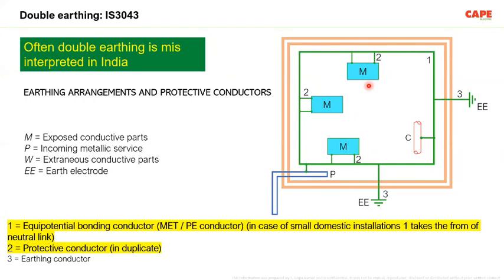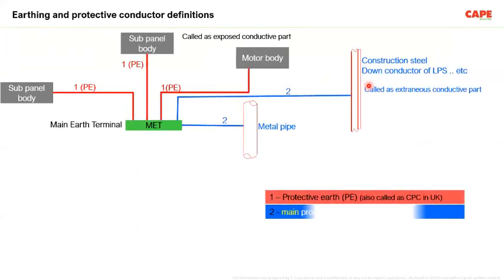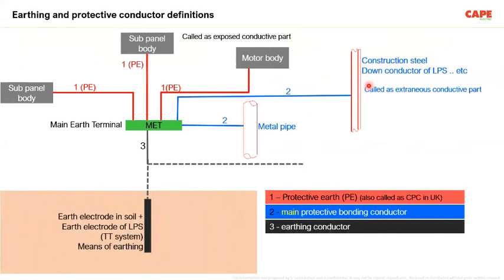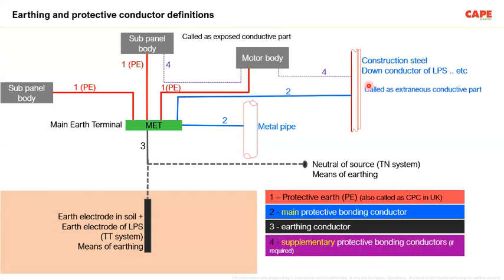What double earthing means is, you have a protective equipotential bonding in your building, and you are buying a new motor. The motor earth terminal must be connected to the equipotential bonding system with 2 connections for redundancy. This is double earthing. It has nothing to do with 2 earth pits in soil. Every building must have a protective equipotential bonding, which is written everywhere in the standards and regulations. I often explain this picture, so people know it very well.